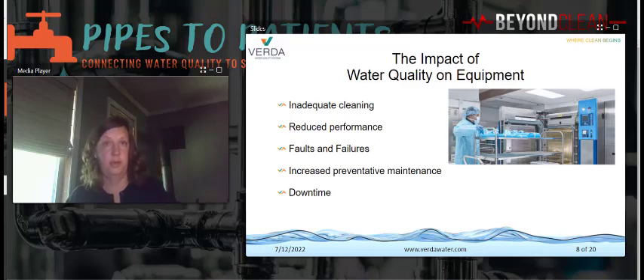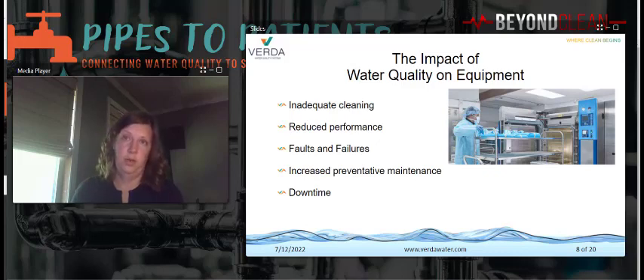For example, with reverse osmosis, high pH water will reduce the effectiveness of RO membranes, resulting in low-quality product water with too many dissolved solids remaining in the water to be used as critical final rinse. Likewise, tepid to hot water feed over 77 degrees Fahrenheit to the RO will result in degraded water quality. Lower temperature feed water results in higher quality product water, but at the sacrifice of product water flow rate.